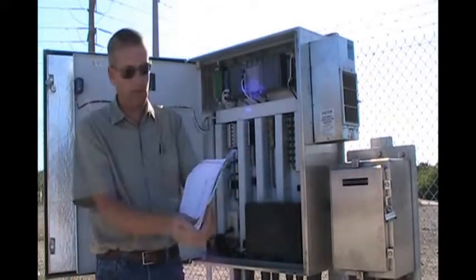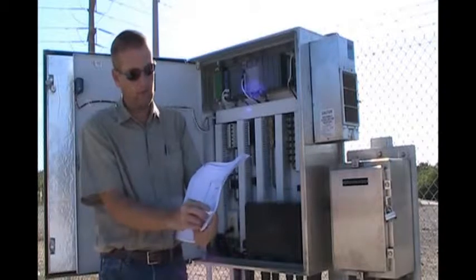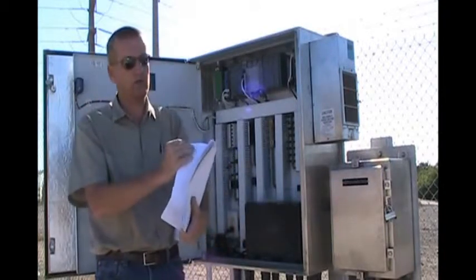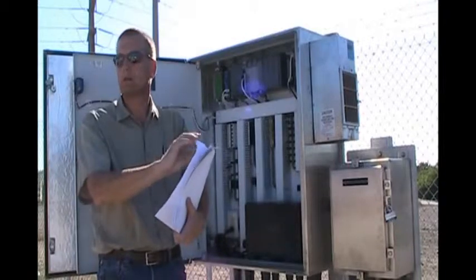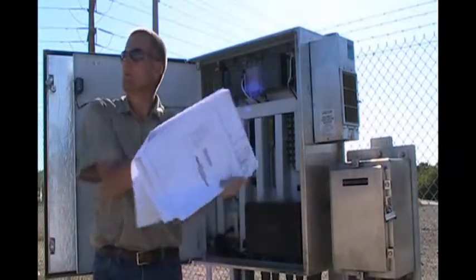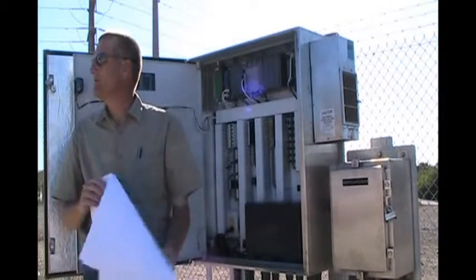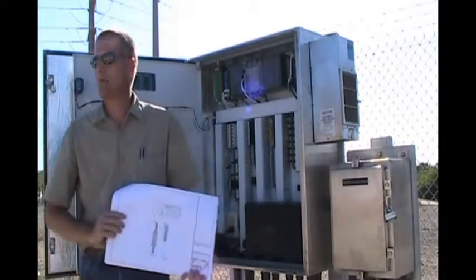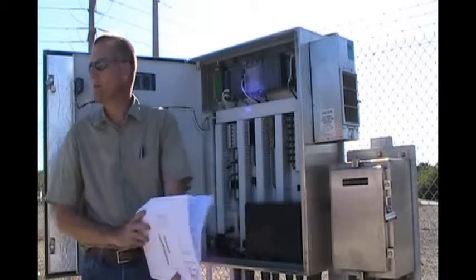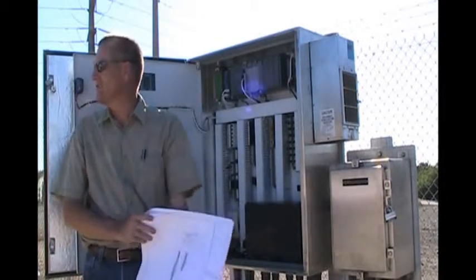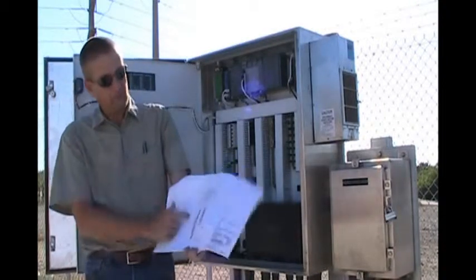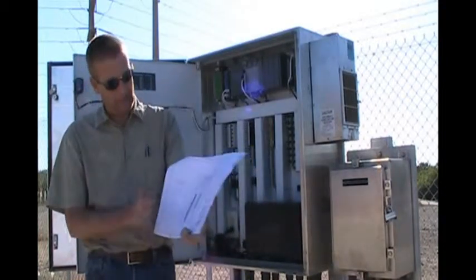The next thing you'll see will be the terminal blocks and the PLC and the radio. And this is solar, so there's no UPS in this one. It has its batteries. We did the 48-hour test to make sure it ran without being connected to solar panels. We actually went like 68 or 70 hours, and it was still doing fine. So that's been completed.